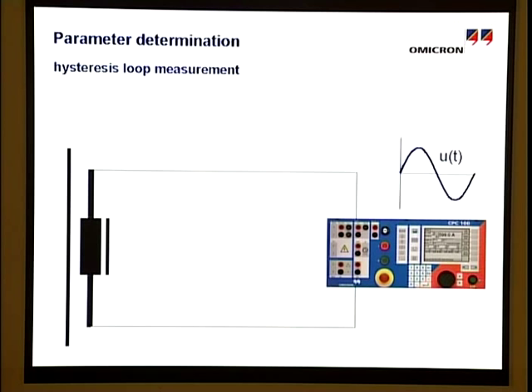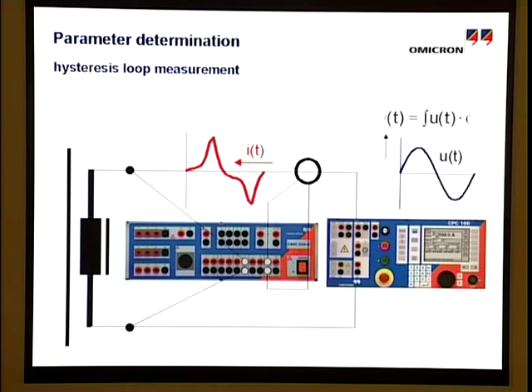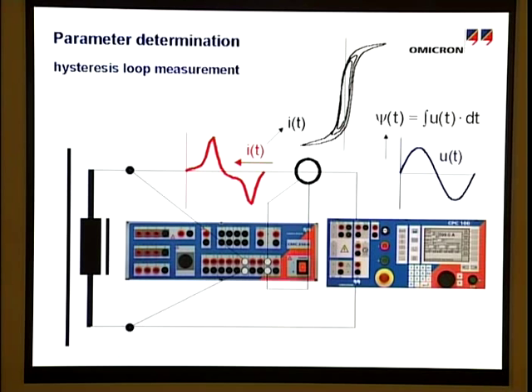The non-sinusoidal current and the voltage are measured by the CMC256 via its analog inputs. When overlapping the magnetic flux derived from the voltage via integration and the measured magnetizing current point by point, the hysteresis loop for a specific voltage is obtained. By increasing the voltage until distinct saturation, the saturation hysteresis loop can be measured. For this, voltages up to 2000 volts are required.